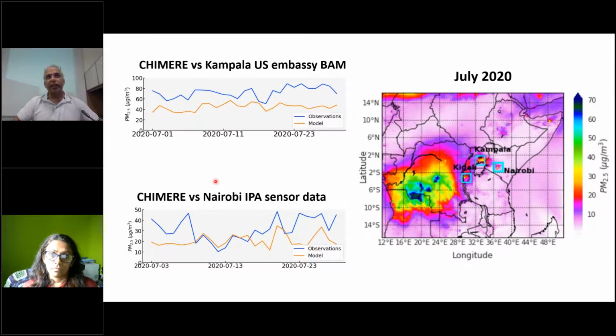And at higher relative humidity, depending on the particle composition, for example, if there is some sulfate or hygroscopic organic aerosol in the mix, then that will take up water and the aerosols will grow in size. And the nephelometer basically looks at the scattering of the particle itself. It's not looking at the size of the particle. Actual PM standards, for example, are based on dry aerosols. So either you can dry the incoming stream of aerosols and remove any water taken up by the aerosol, or you need to correct for the hygroscopic growth of the aerosol before comparing it to reference monitors. So that's why it'll end up reporting higher than reference monitors.